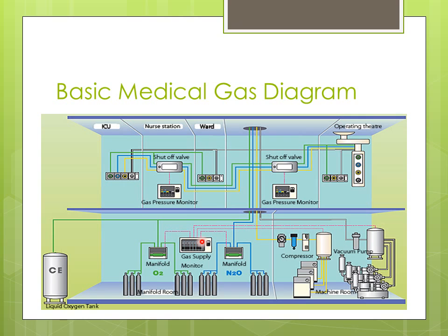The other thing, is it monitored? Well, not very likely. There's probably a very good chance that this gas monitor is not monitored 24/7 as is required, or in a location where it can be monitored. This is obviously a storage room, and there probably aren't people in here. Might be in engineering or something like that. But even then, is that monitored 24/7? That's one of those code requirements. So just a couple of things when you look at these things like this. Again, this picture wasn't designed to be perfect, I know that, but as you start getting a trained eye, you'll start seeing these things. They'll start jumping out at you as you look at designs of things like this.